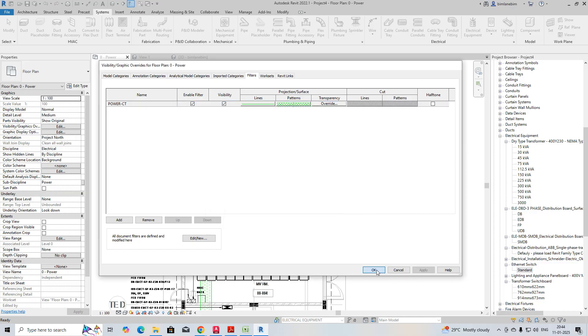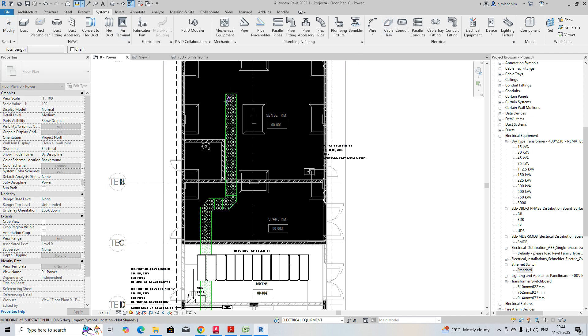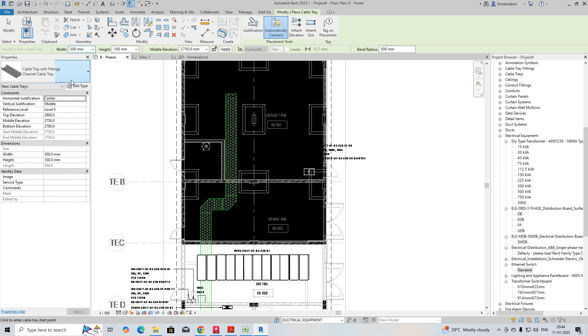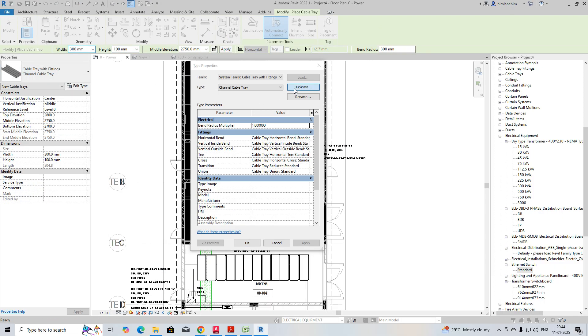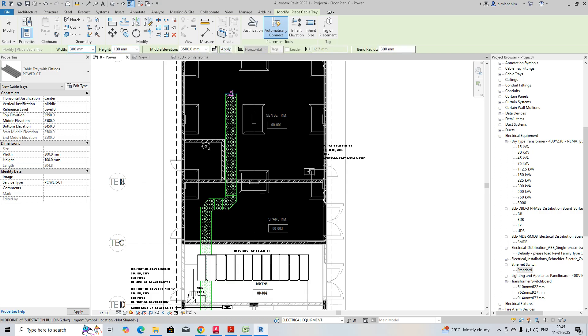Click OK, Apply, OK. Now we need to draw the cable tray. Measure the size — it's 300mm. Go to Cable Tray, duplicate it, name it 'Power CT', click OK. Set the elevation to 3500mm and set the service type to 'Power-CT' so it automatically applies, then run as per the routing.